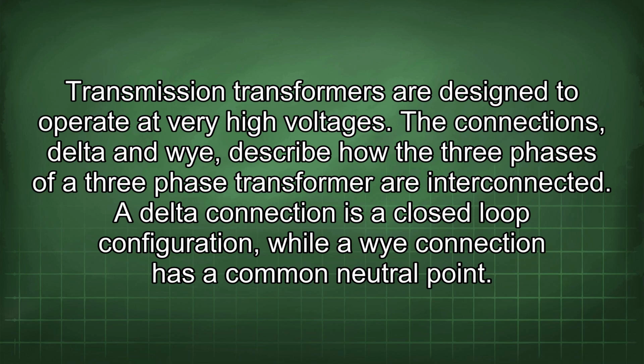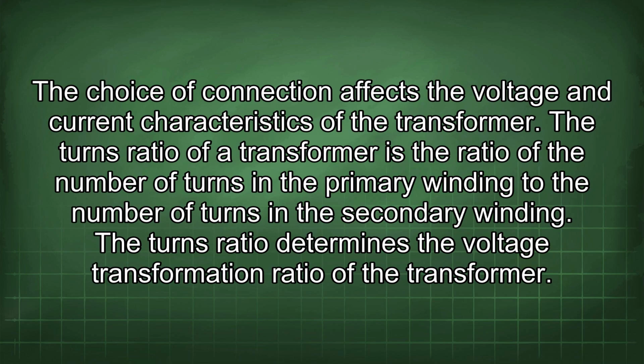The connections, delta and Y, describe how the three phases of a three-phase transformer are interconnected. A delta connection is a closed-loop configuration, while a Y connection has a common neutral point. The choice of connection affects the voltage and current characteristics of the transformer. The turns ratio of a transformer is the ratio of the number of turns in the primary winding to the number of turns in the secondary winding. The turns ratio determines the voltage transformation ratio of the transformer.